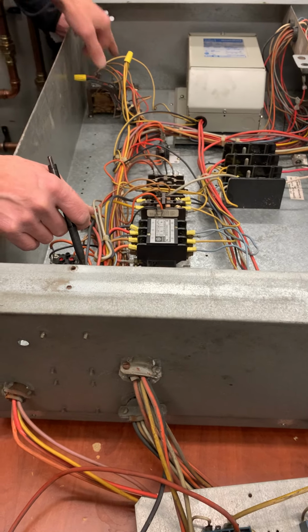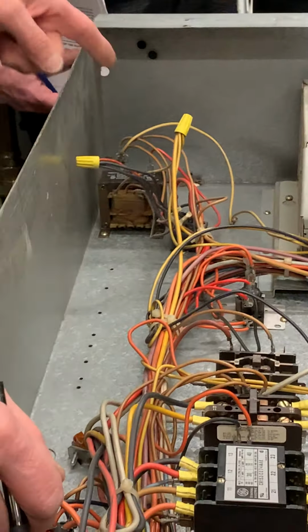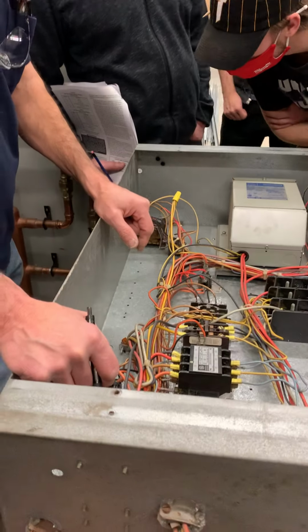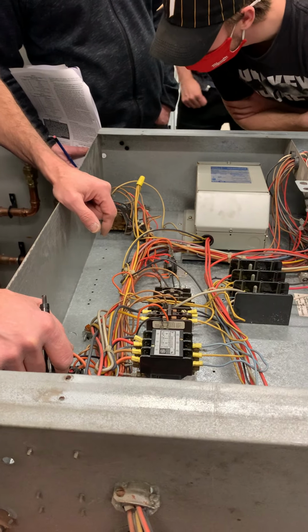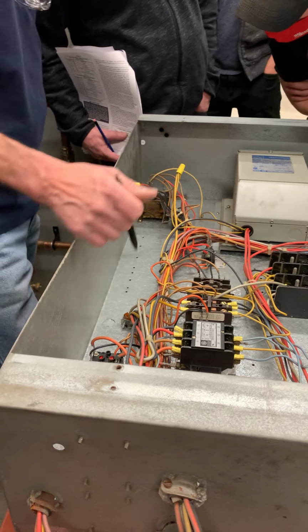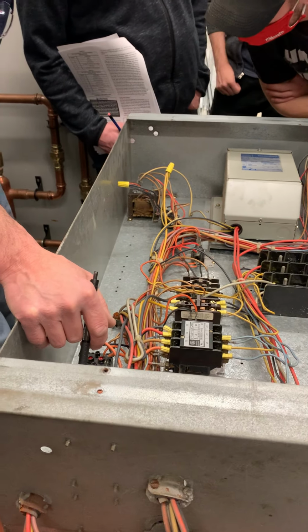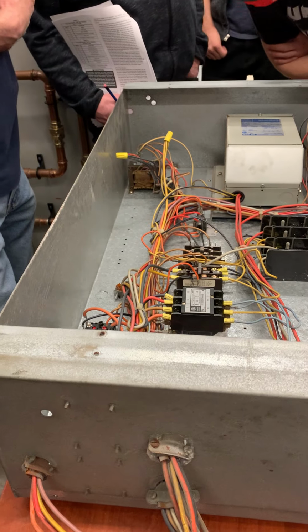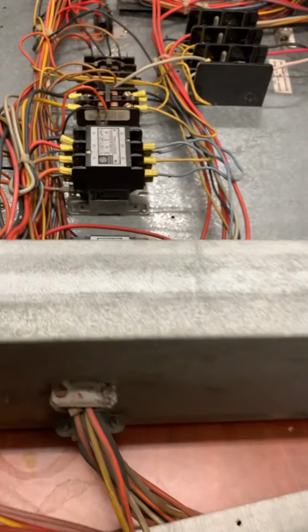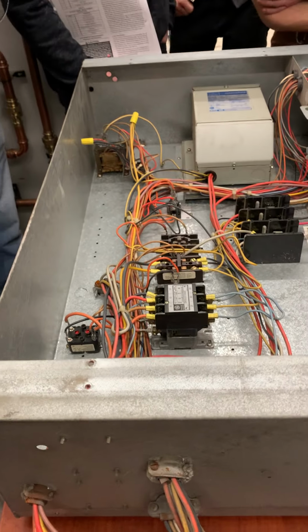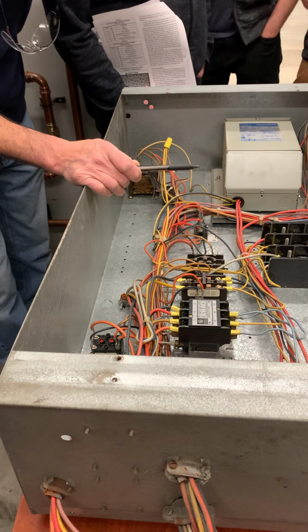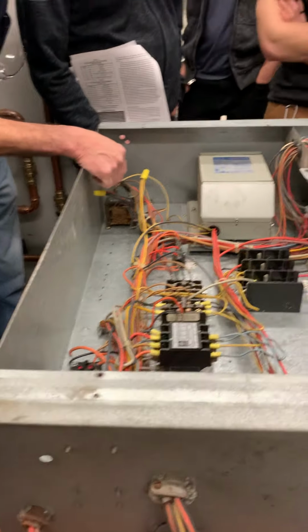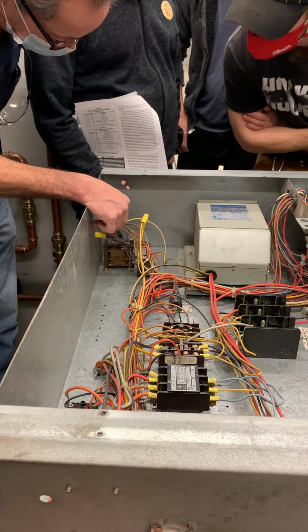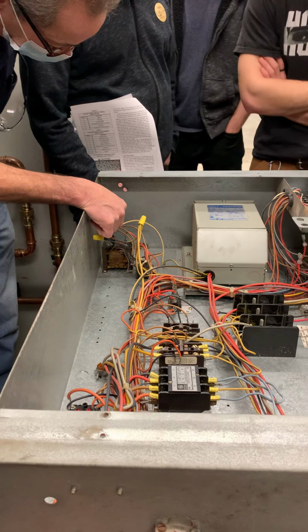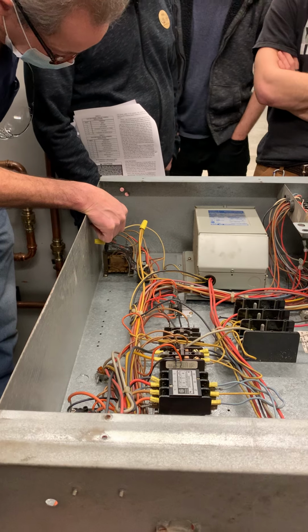Next, what's this item right here? Transformer. What's the voltage on the transformer? 24. Okay, so I agree the secondary is 24. What's the primary? 230, is that what it says there? Oh, I don't know. I'm going to have to put my glasses on now. You're making my life difficult. It says 460, 230, 200. There's 3 different voltages there. Well, hang on a second now. What the hell are they talking about here? Because I'm looking here and they say 460 volts, 230 volts, or 208 volts, or 200 volts. That is weird.